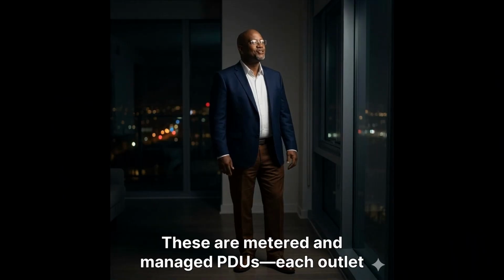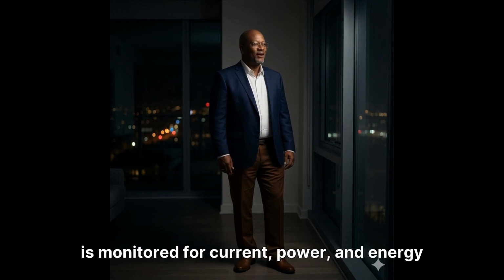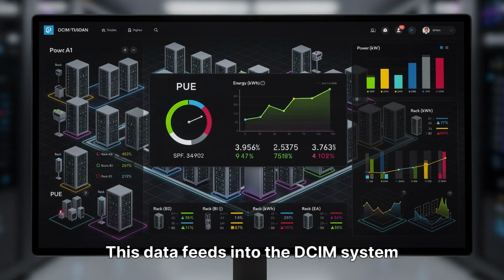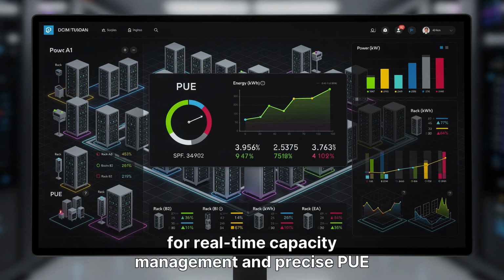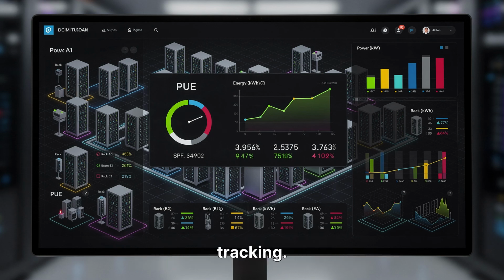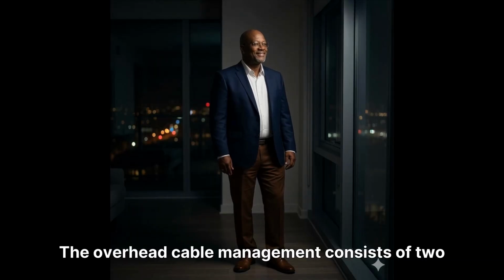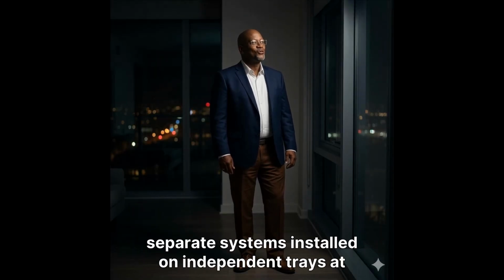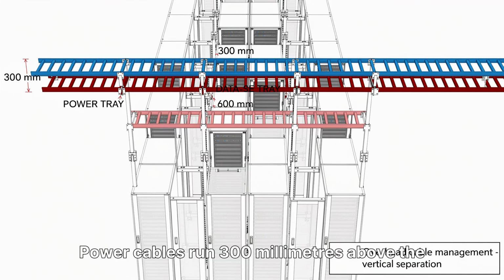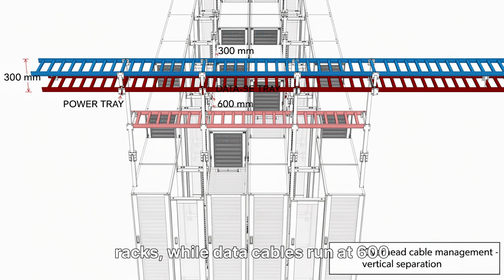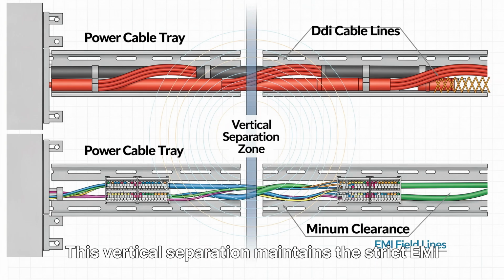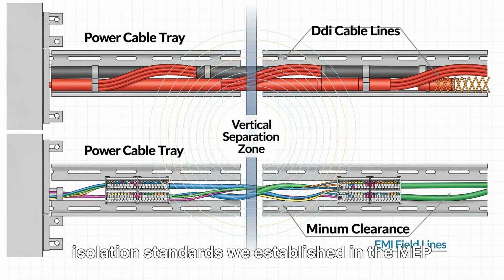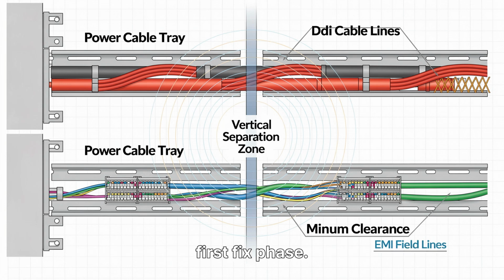These are metered and managed PDUs. Each outlet is monitored for current, power, and energy consumption. This data feeds into the DCIM system for real-time capacity management and precise PUE tracking. The overhead cable management consists of 2 separate systems installed on independent trays at different heights. Power cables run 300mm above the racks, while data cables run at 600mm above. This vertical separation maintains the strict EMI isolation standards we established in the MEP first fix phase.